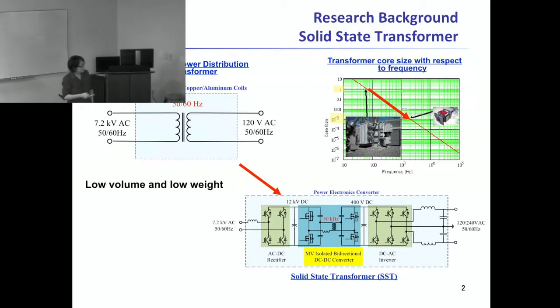To reduce the volume and the weight, this is a widely accepted configuration of the solid state transformer. It consists of three conversion stages: AC to DC rectifier, medium voltage DC to DC converter, and DC to AC inverter. The DC to DC converter plays a key role to provide high frequency isolation, high efficiency, and high power density for the whole SST.